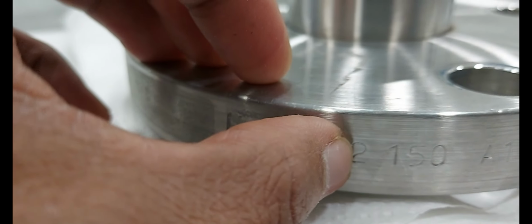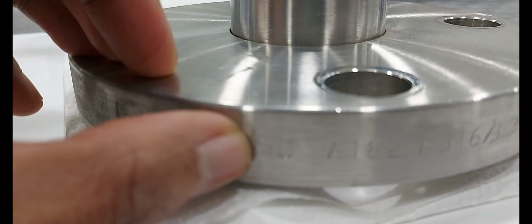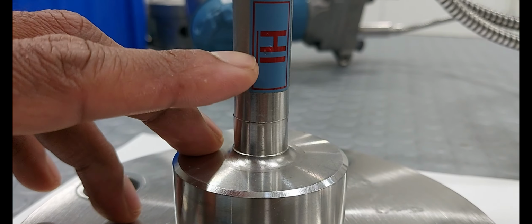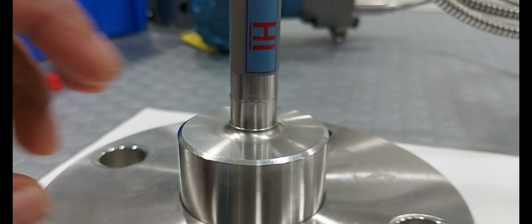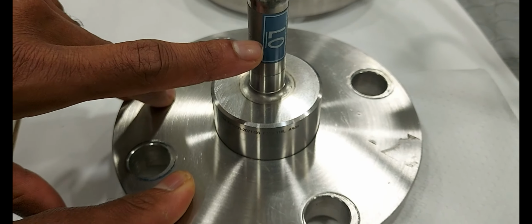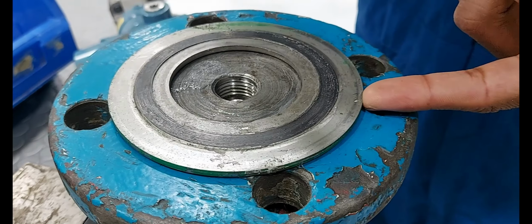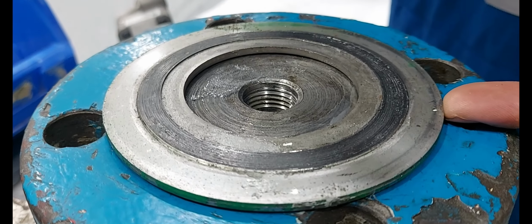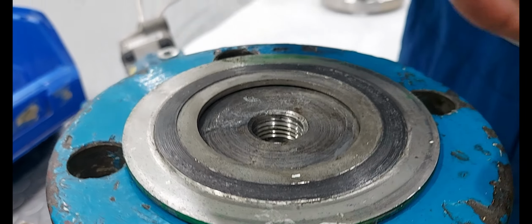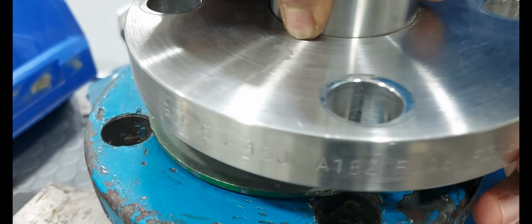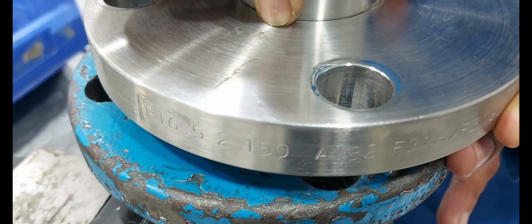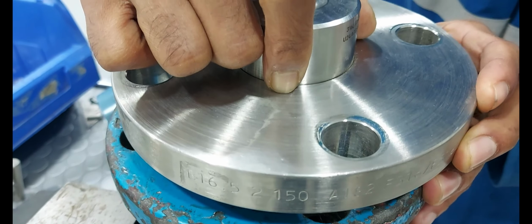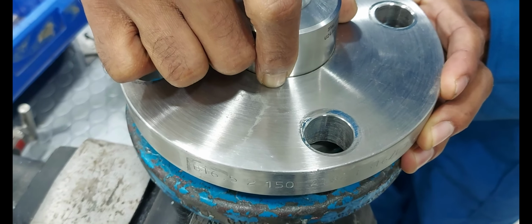Flange size 2 inch 150, high side sensor, low side sensor. This is a gasket, 2 inch 150 gasket. Next we are installing the temporary flange. Next we are installing the stud tie bolt.